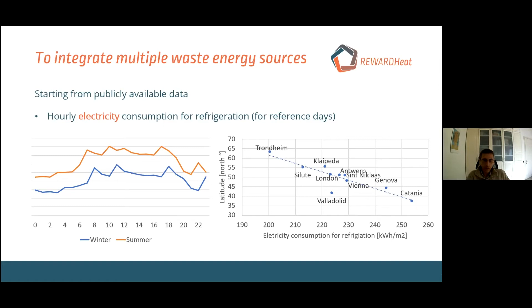What we are doing is trying to understand what kind of substation can be installed in the refrigeration system to recover heat into different kinds of district heating and cooling networks, and what the equivalent COP is - the amount of electricity needed to recover this waste heat in the network, depending on whether there's a heat pump in the substation. Out of this, we want to provide a distribution of waste heat available, at what temperature, during the year.